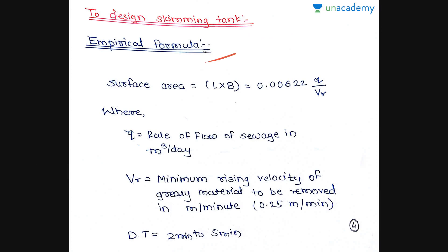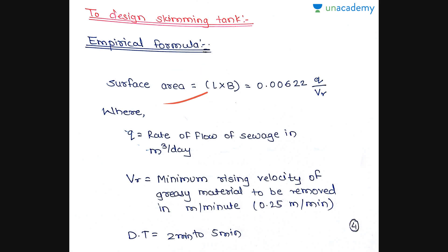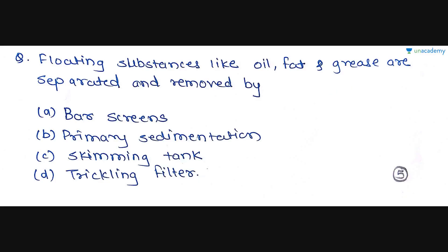Next is the design of the Skimming Tank. An empirical formula is given for this: Surface Area = L × B = 0.00622 × q / Vr, where q is the rate of flow of sewage in cubic meters per day, and Vr is the minimum rising velocity of greasy material to be removed in meters per minute — generally 0.25 m/min. This formula is very useful and questions may be asked on it.